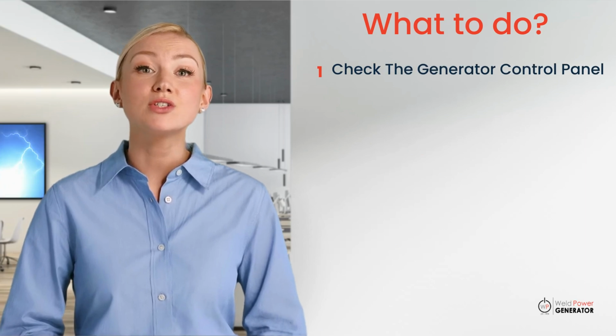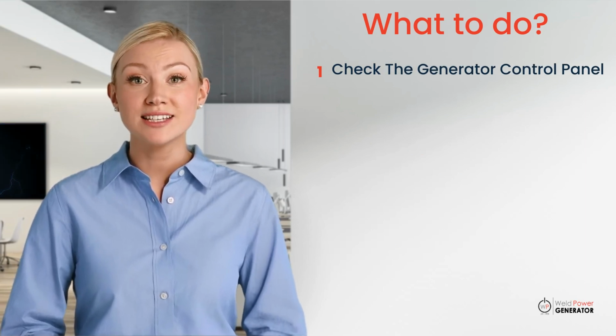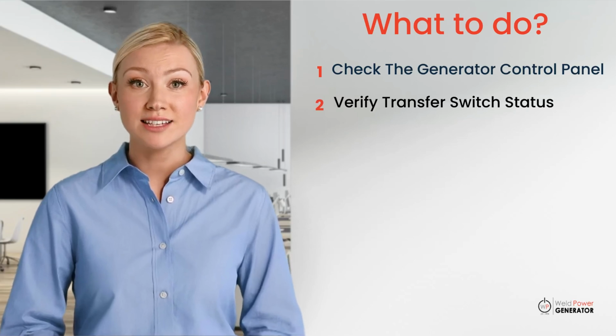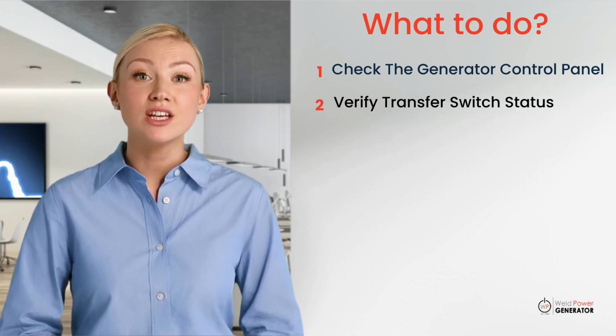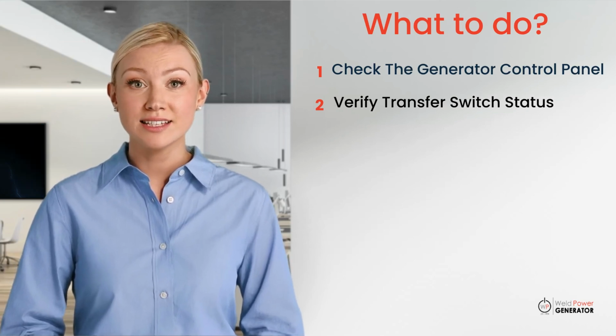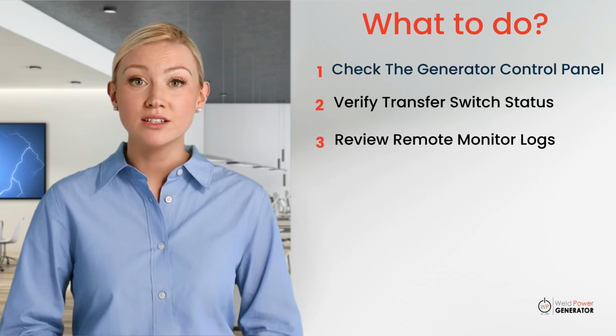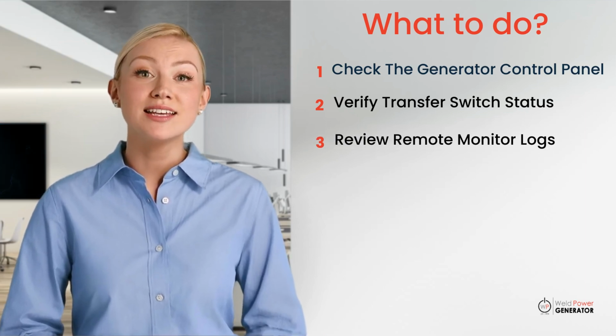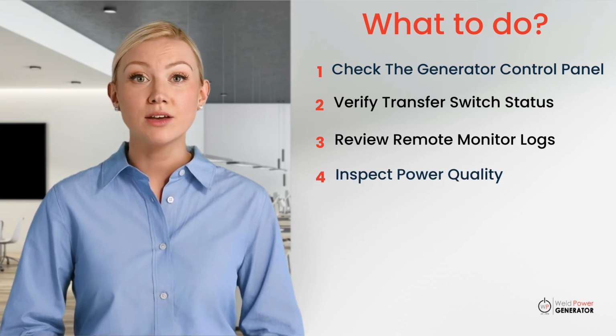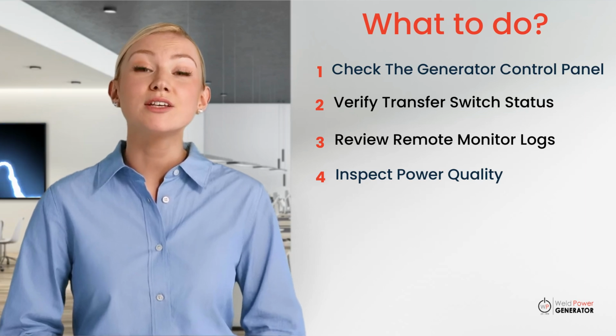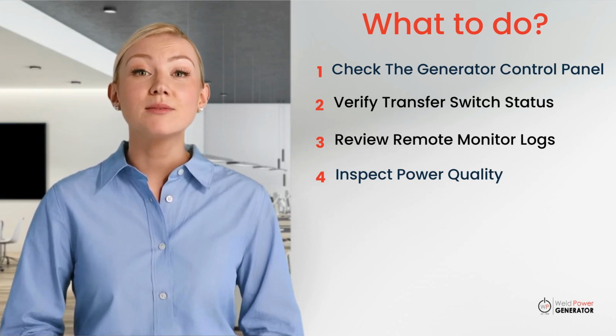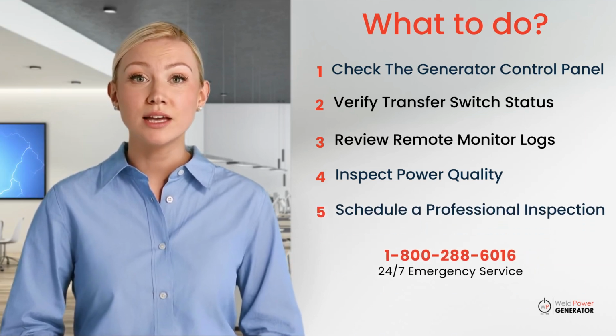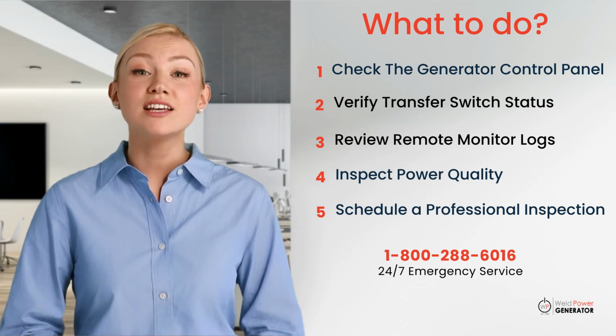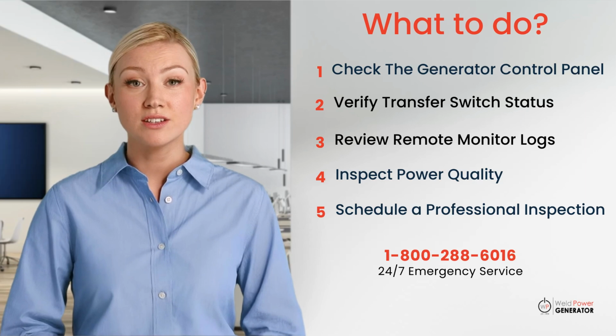If your generator is running unexpectedly, here are the steps you should take. Check the control panel. Look for alerts, fault codes, or exercise timers that may indicate a routine self-test. Verify transfer switch status. Ensure that the ATS is not calling for generator power due to a malfunction or incorrect settings. Review remote monitoring logs. Check if the generator was remotely activated for maintenance or load management. Inspect power quality. If possible, monitor voltage and frequency fluctuations in your utility power that may be triggering the generator. Schedule professional inspection. If no clear cause is found, consult a generator technician to perform a diagnostic evaluation.